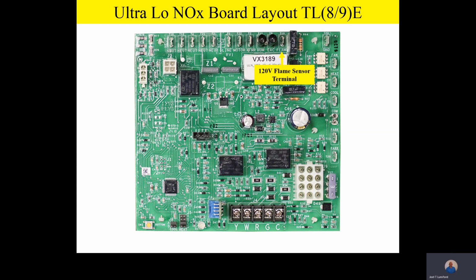This is our 120 volt flame sensor terminal. Now, team, please remember this as well. Anytime the furnace has power to it, the flame sensor will be active. And so the flame sensor by National Gas Code has got to be active all the time, year round. So anytime there's power on the furnace, the 120 volt flame sensor terminal will be energized.